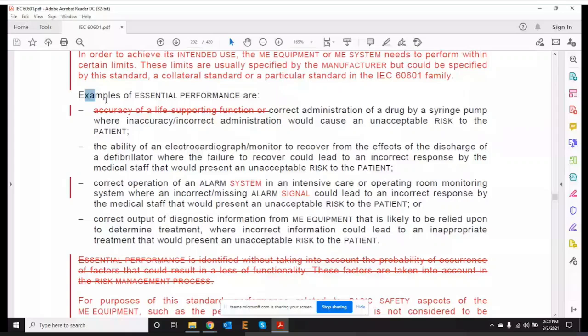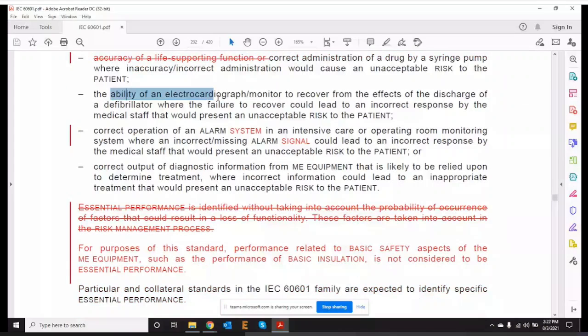So if you see the examples of essential performance, this performance test is carried out by the certification body. The ability of the electrocardiograph or monitor to recover from the effect of the discharge of a defibrillator, where the failure to recover could lead to an incorrect response by the medical staff. And this is an unacceptable risk to the patient.